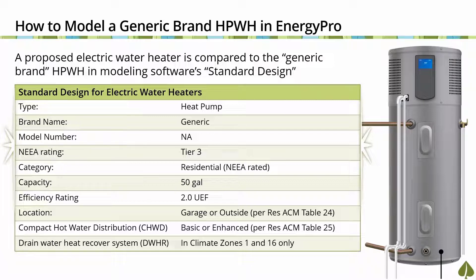Please refer to table 24 in chapter 2 of the residential ACM reference manual for more information. In addition to the water heater specifications, the prescriptive requirement also includes a compact hot water distribution or CHWD system using either the basic credit or enhanced credit depending on the climate zone. When the project is located in either climate zones 1 or 16, the standard design for a heat pump water heater also includes a drain water heat recovery system or DWHR system.